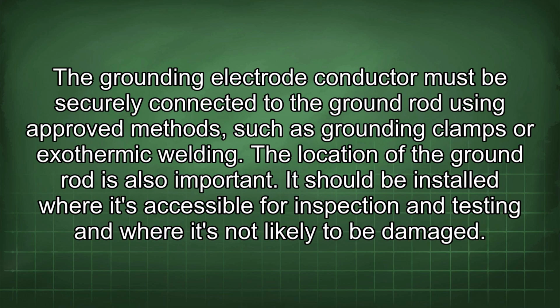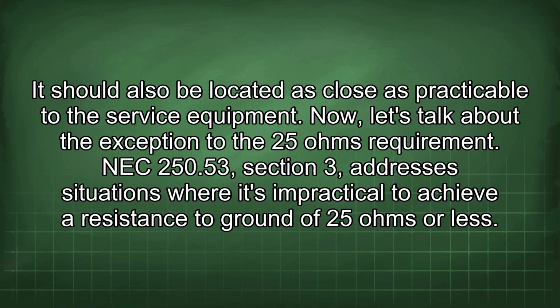The grounding electrode conductor must be securely connected to the ground rod using approved methods, such as grounding clamps or exothermic welding. The location of the ground rod is also important. It should be installed where it's accessible for inspection and testing and where it's not likely to be damaged. It should also be located as close as practicable to the service equipment.